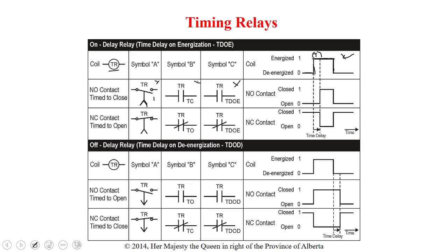The fact that the contact is open means it's a normally open. So it's a time delay, normally open, time delay on energization. Other ways to write that, you can see on the right here, we've got a normally open contact drawn, and it says time to close. So that would be another way to write it, or just a normally open contact with TDOE written beside it.